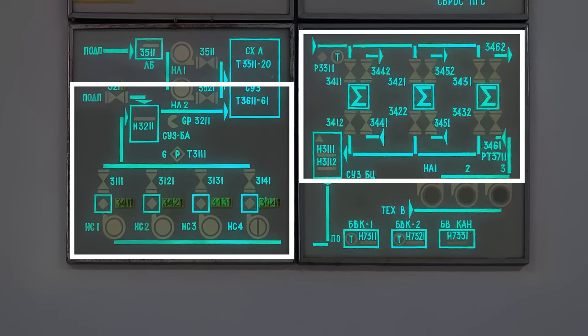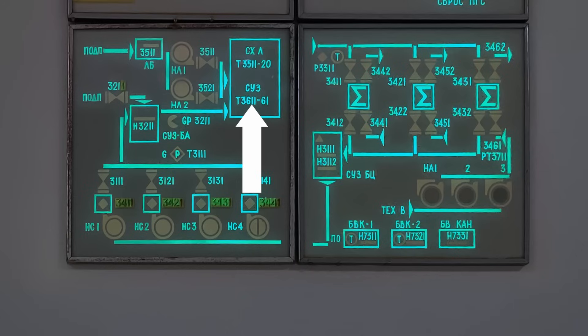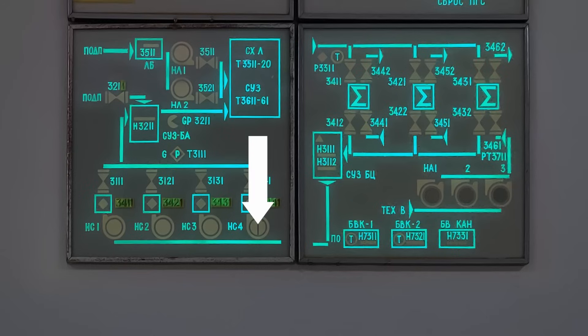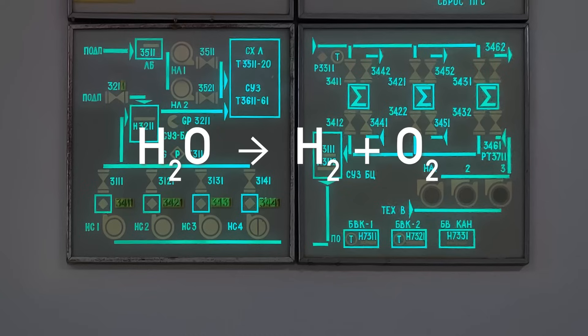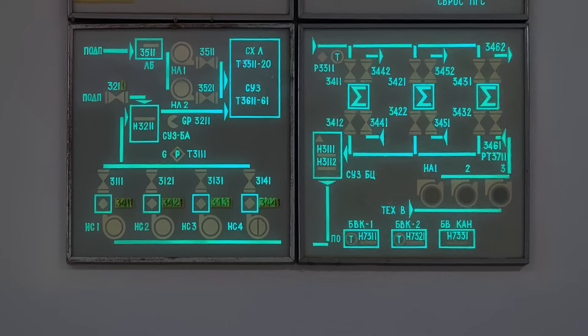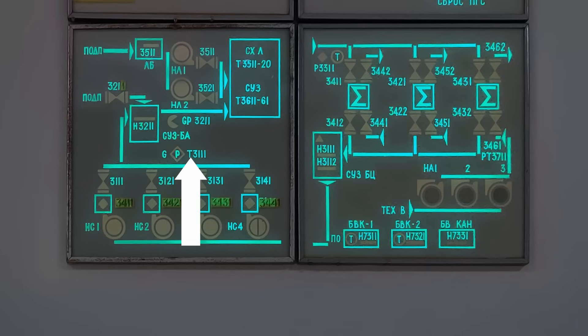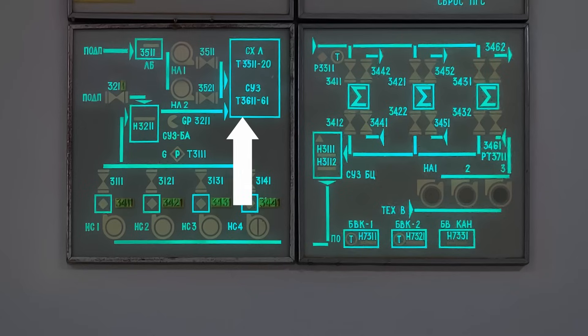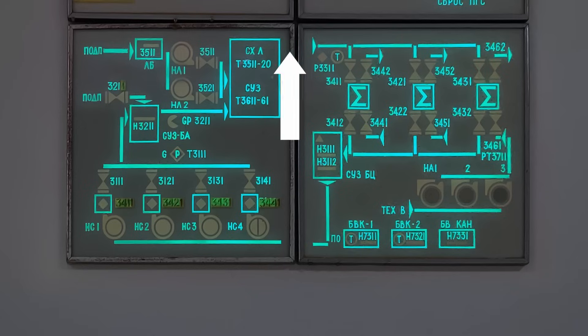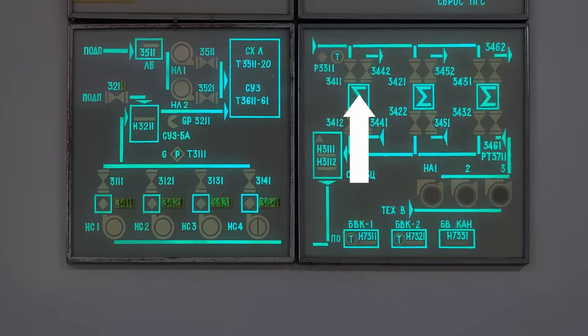Ok, and now let's move on to a more complex system, so this is the cooling of control rod channels which are marked with this notation. Technically it is a closed loop of purified water that starts from this tank and is pumped by these pumps. But because this water passes through the reactor core, radiation can split some amount of it into hydrogen and oxygen, which is not really safe. So after pumps, it goes through these devices that strip out those gases. Then it goes through the receiver tank and inside the control channels to absorb heat. It becomes hot after it, so then it is cooled in heat exchangers before returning to the tank.